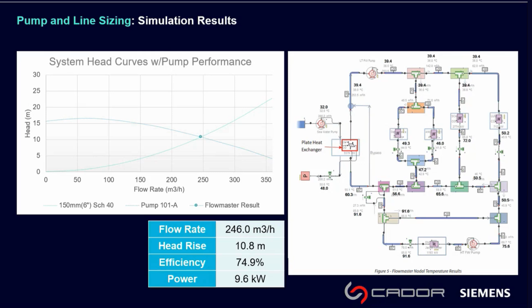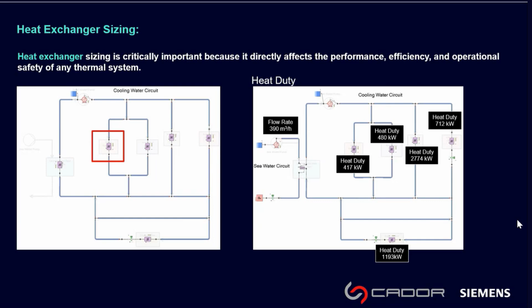Next, how do you model or size heat exchangers? On the left is the cooling circuit of the model, and the red square indicates a heat exchanger model from Flowmaster. There are several ways to model heat exchangers depending on the data available — for example, if you simply have the heat duty, or Q, you can enter that and Flowmaster will calculate the heat transfer, inlet-outlet temperature, flow rate, and so on, as shown on the right. This lets you calculate and predict the performance, efficiency, and thermal behavior of the model.